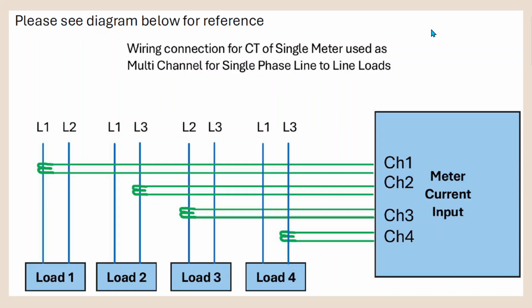This diagram is showing how you will connect the CT to the meter. As explained before, if the load is line 1 and line 3, you will install the CT in line 3. If the combination is line 1 and line 2, you will install the CT in line 1. If your load is line 2 and line 3, you will install the CT in phase L2. So it is always required to know the phase of each line that you are installing for all the loads: load 1, load 2, load 3, and a maximum of load 4 for a single-channel meter.